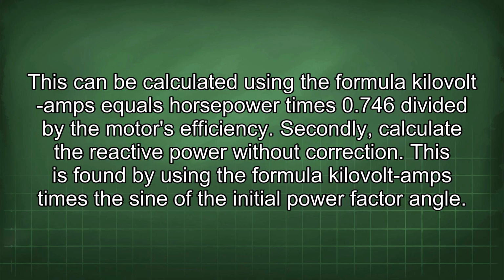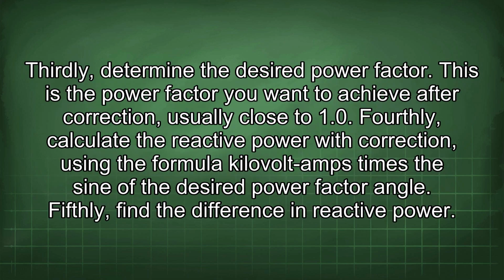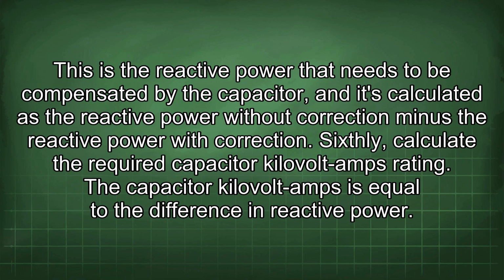Secondly, calculate the reactive power without correction. This is found by using the formula kilovolt amps times the sine of the initial power factor angle. Thirdly, determine the desired power factor. This is the power factor you want to achieve after correction, usually close to 1.0. Fourthly, calculate the reactive power with correction, using the formula kilovolt amps times the sine of the desired power factor angle. Fifthly, find the difference in reactive power. This is the reactive power that needs to be compensated by the capacitor, and it's calculated as the reactive power without correction minus the reactive power with correction.